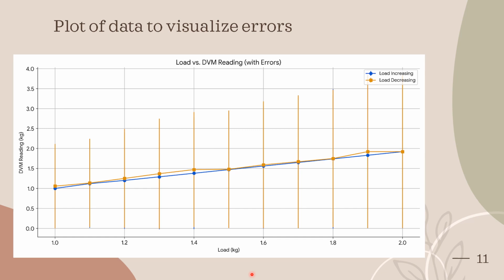As mentioned earlier, there is a variation in both the lines, that is load increasing and load decreasing value. These deviations are due to the hysteresis loss. I can explain this with an example. Suppose we put the cantilever beam in the 2 kg state for a longer period of time, due to which we will get some deformation in the cantilever beam, and the deformation will lead to some errors. The deformation will slowly fade away, but until then we will get slightly changed values, which is actually error from the original value, and this error corresponds to the deviation in the data points of the yellow and the blue line.